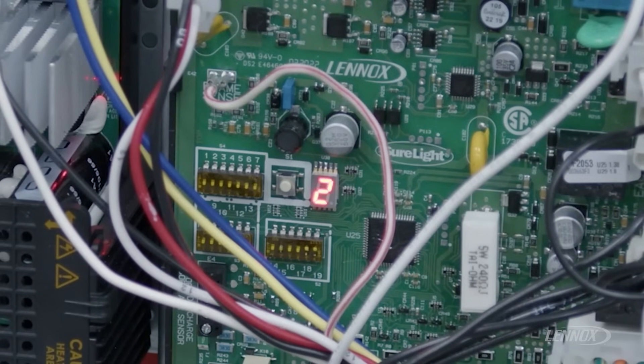As you can see here, our 7-segment LED readout is displaying an E201 code. The description of this fault code reads Indoor Blower Motor Fault, and if we look into some expanded data on that code, our applicable component would be our furnace, more specifically our blower motor, and it's a service urgent code.